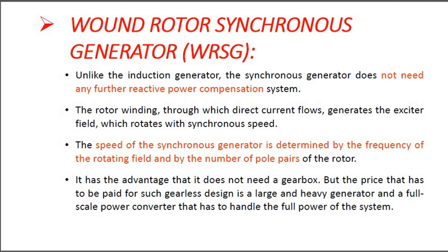It has the advantage that it does not need a gearbox, but the price that has to be paid for such gearless design is a large and heavy generator and a full-scale power converter that has to handle the full power of the system. So gearless operation requires complicated design and high cost.